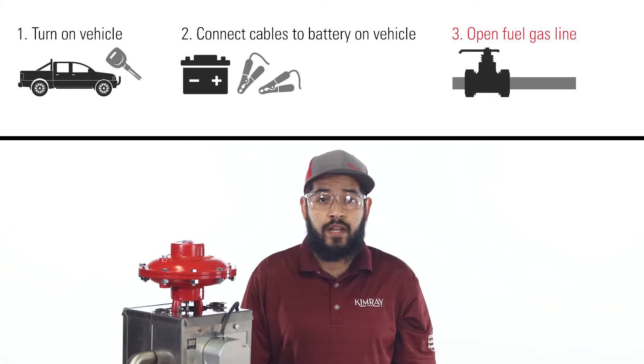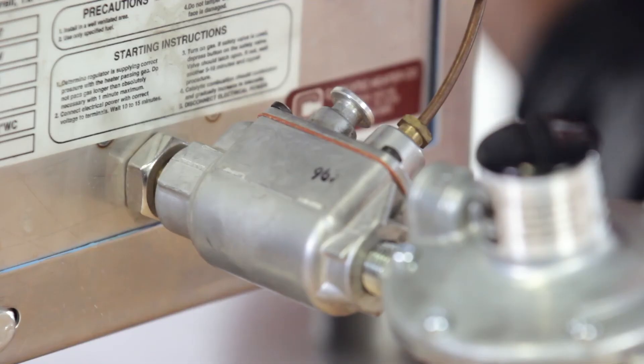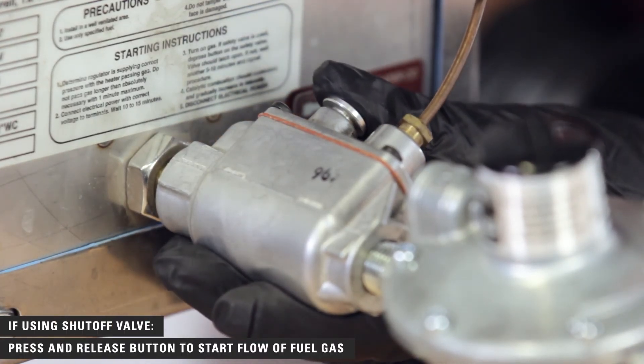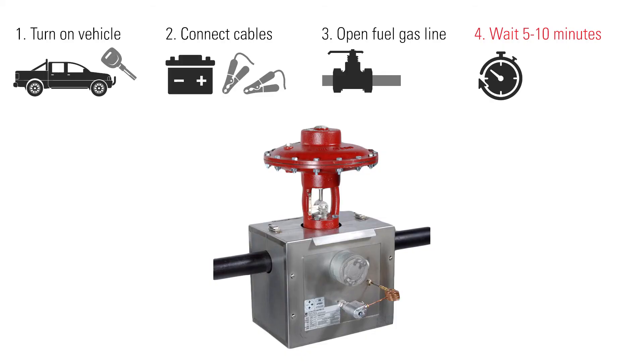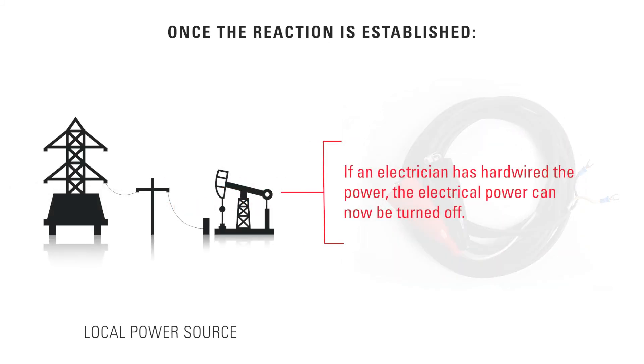Once the catalyst bed has been preheated, open your fuel gas line. If you are not using a shut-off valve, simply opening the fuel gas line will start the catalytic reaction. If you do have a shut-off valve installed, press and release the button to start the flow of fuel gas to the heater. Leave the connection for 5 to 10 minutes until the catalytic reaction is fully established — this will be indicated by a rapid rise in face temperature. Once the reaction is established, disconnect the cables from your vehicle. If an electrician has hardwired the power, the electrical power can now be turned off.